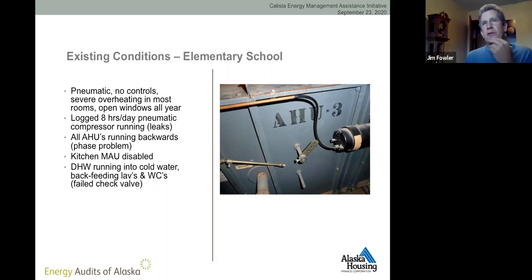The kitchen makeup air unit was disabled. So every time the exhaust fans were turned on in the kitchen, they're blowing all the heated air out of the building. And significantly, the domestic hot water was running into the lavatories, the toilets and the lavatory sinks because of a failed check valve. So we had hot water in the toilets, and we had hot water on the cold water side and the hot water side of the sinks in the building. So that's just a snapshot of what was wrong.